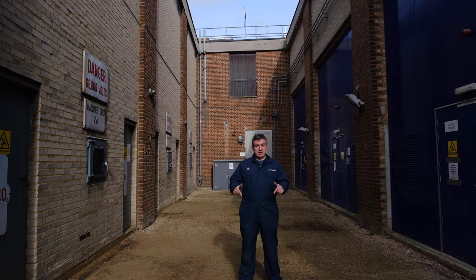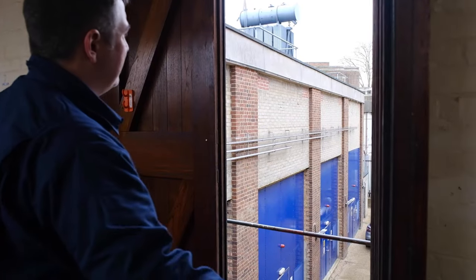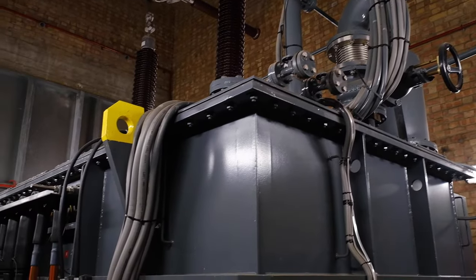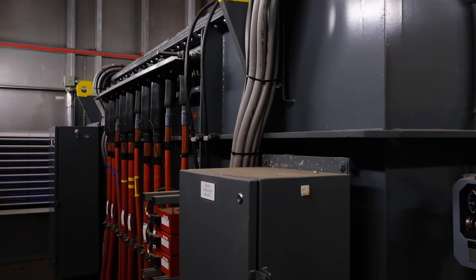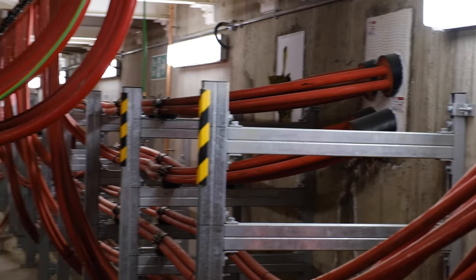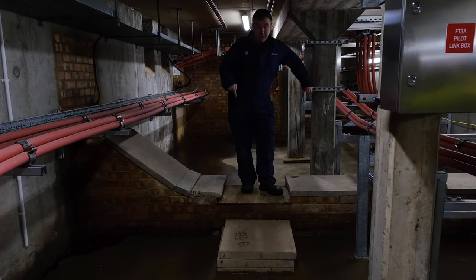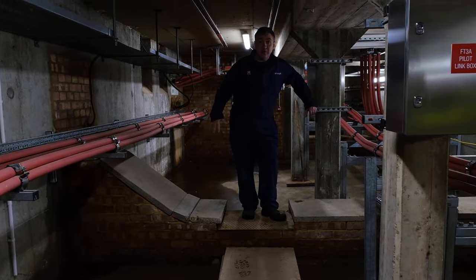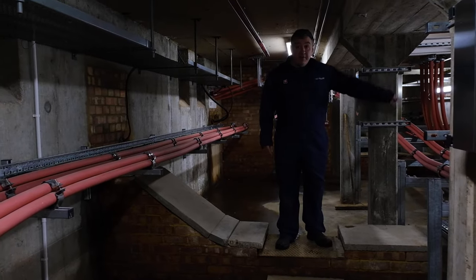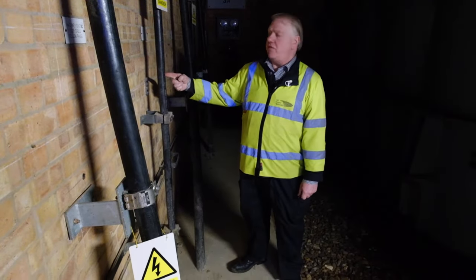This site at Edwards Lane has been a linchpin of electricity supply — very much a hub for 115 years for Stoke Newington — and to this day it's still alive, providing and connecting you with your daily energy. In amongst all the new cabling installed just a couple of years ago, beneath my feet we have the original 1960s 66,000 volt cables. There are four troughs to protect them; they come from Hackney and connect into the transformers. This is the 66 kV cable coming in from Hackney.